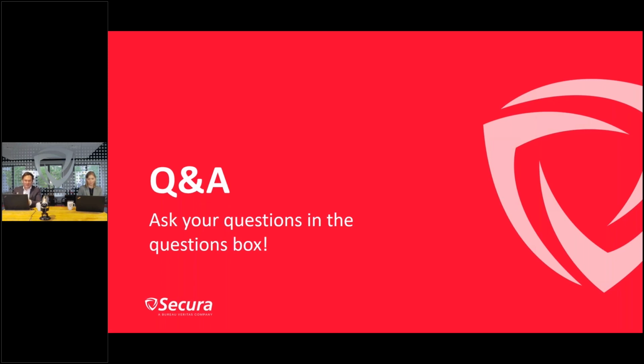Yeah, that's a good question. Well, to start with, we always recommend standards, best practices, or international frameworks as a good reference to address regulations. Regulations, by definition, are quite vague. They point toward a higher-level view of the controls or requirements you need to include in your product, not only for medical devices but other regulations too. But they don't say explicitly what needs to be done, just the direction. For what needs to be done, it's much easier to rely on a standard which takes those high-level controls and transforms them into more concrete requirements, also from a technical implementation perspective.